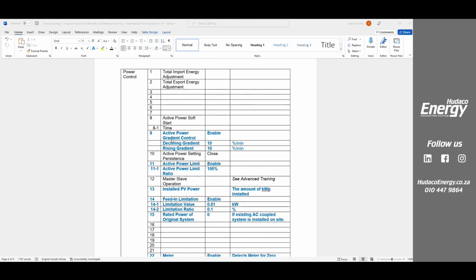This active power gradient control is referring to how fast we are allowing the panels to pick up and slow down. And the main reason they don't just say, okay, come in at 100% and go off at 100% is in homes, you've got things like geysers kicking in, stoves kicking in, kettles and things. You don't want the panels to throw a huge whack at your IGBTs as the geyser kicks in. You can end up damaging your inverter. So they put a rising and a declining gradient on. When it comes out, it's very, very conservative.